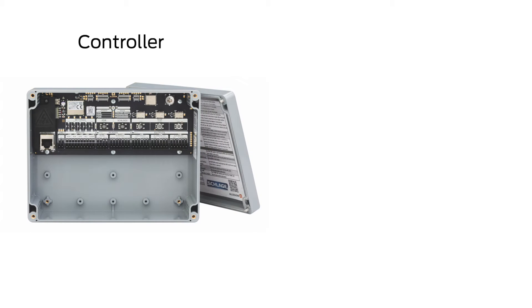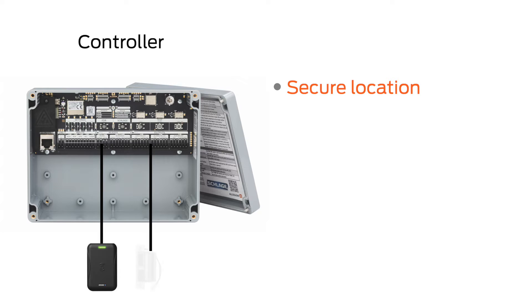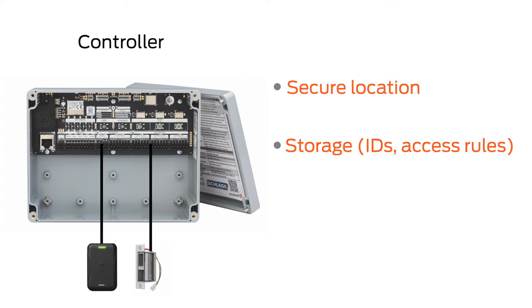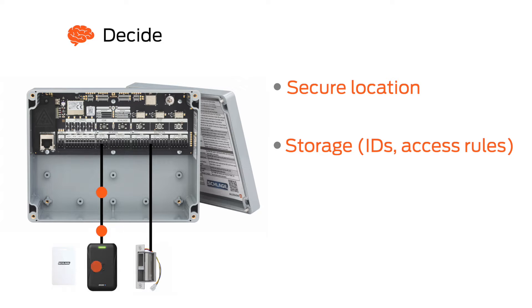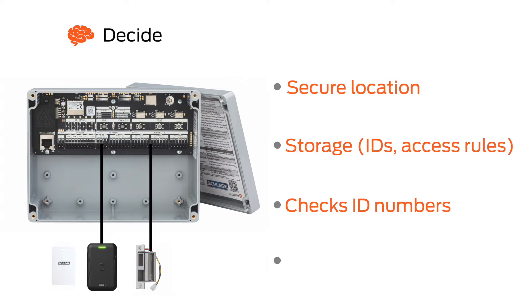The controller is usually a plastic or metal box mounted on a wall in a secure area of the building, and has wiring connections to the card readers and the locking devices. It may also have storage to remember all the valid card IDs and the rules for access. The controller is like the brain of the system — it's the part that does the deciding. When it receives an ID number from one of the readers, it checks to see if it's a valid ID number, and any other conditions for access, such as time of day or what door they're trying to access.